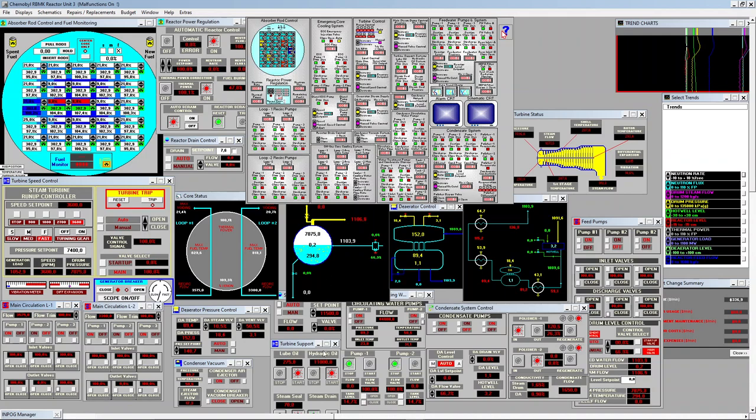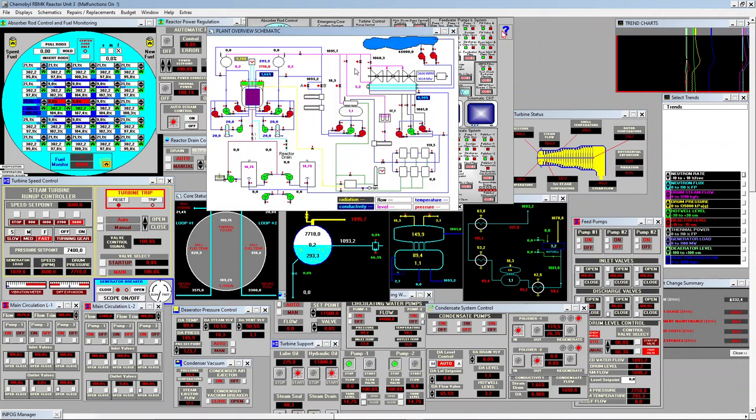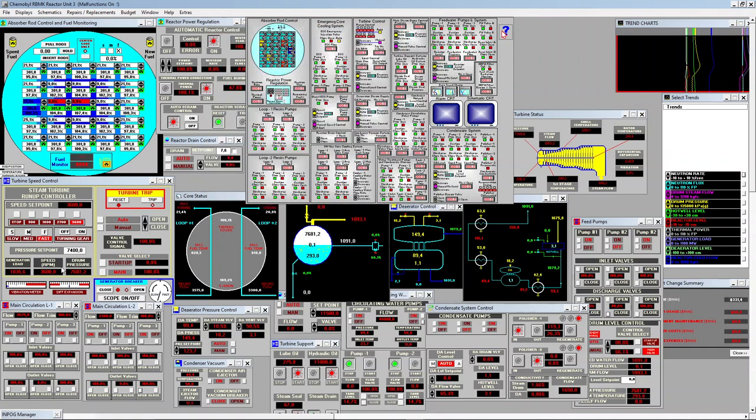Okay, there is a little trick to increase a bit more generated power. You can slightly reduce the pressure set point in the deaerator from 148 to 123. With this pressure, it still works, but because it requires less steam that is collected from the main steam line, there is more available steam going to the turbine to do mechanical work. So this allows to increase maybe around 5 megawatts or so.